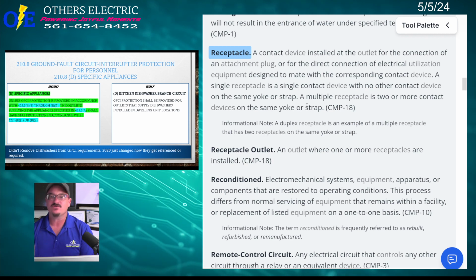So a duplex receptacle that you have in your house with two places to plug something in, that is considered a multiple receptacle. And then if there's just one, it's just single. So I want you to keep that in mind. That's what a receptacle is. Let's look at what an outlet is. Because you notice the outlet is part of the definition of the receptacle, because what the receptacle is attached to, the box that the receptacle is installed into, is the outlet, right? But once you install a receptacle, it goes from outlet to receptacle.